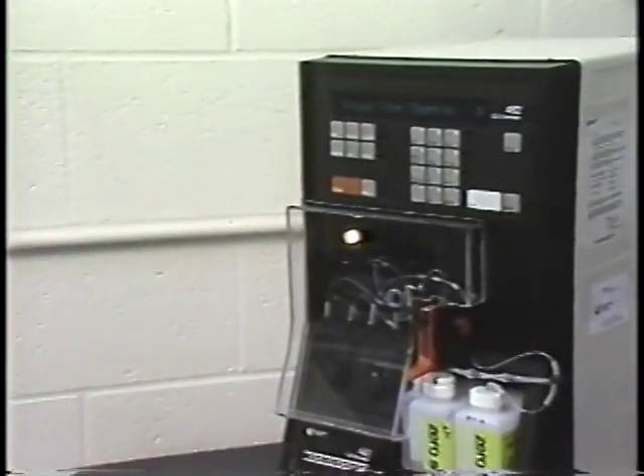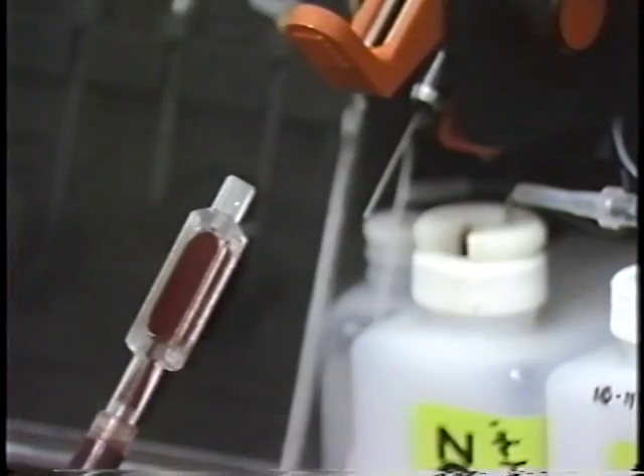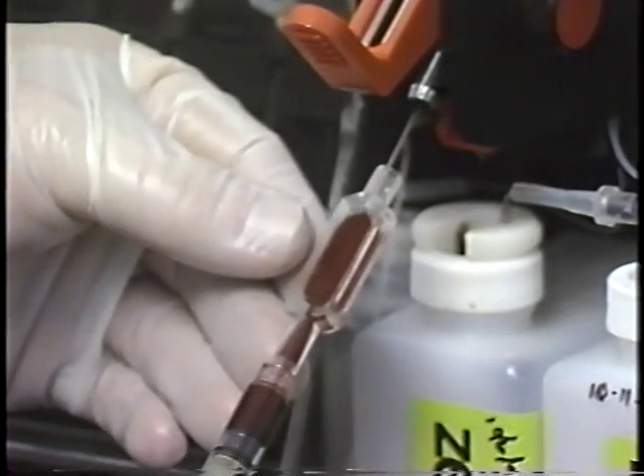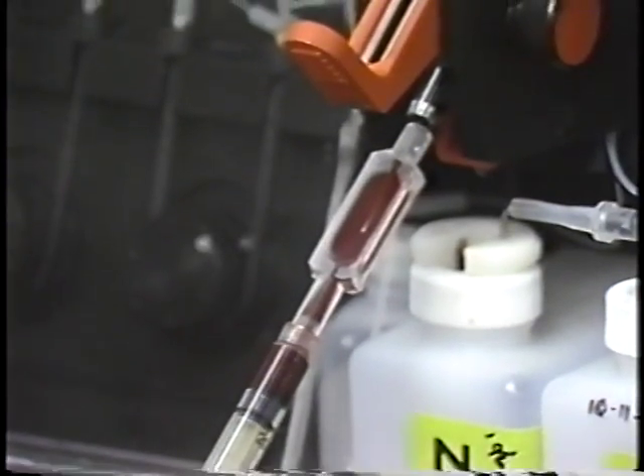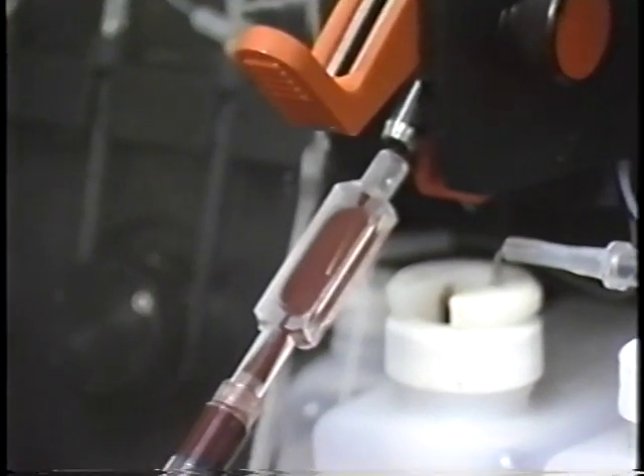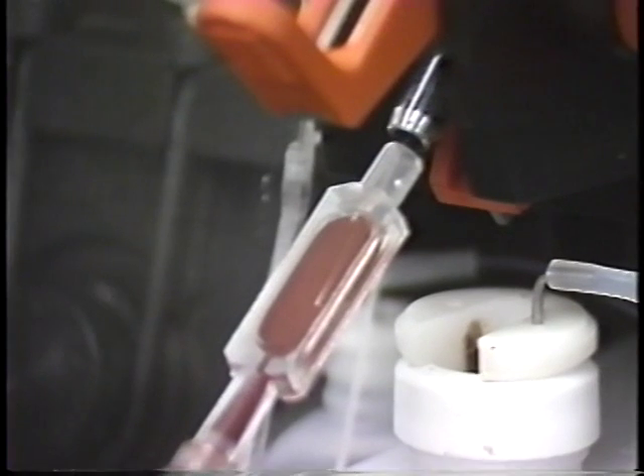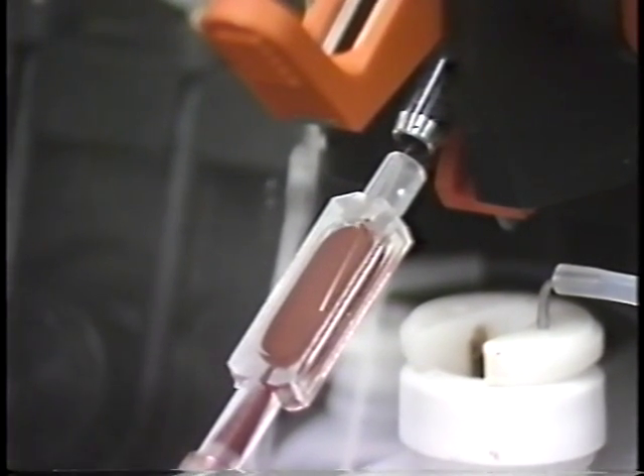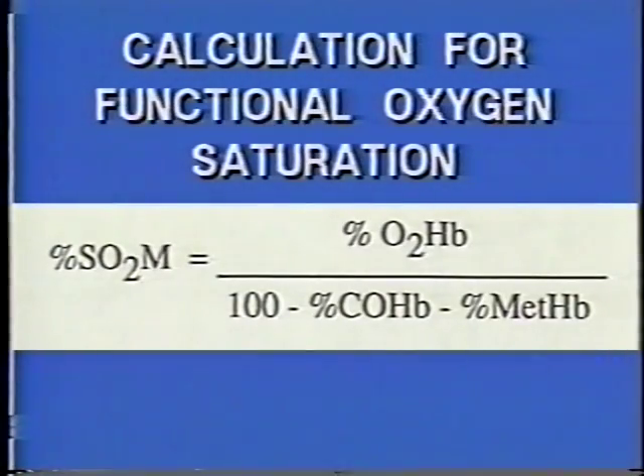Several modern co-oximeters measure oxyhemoglobin, methemoglobin, and carboxyhemoglobin and automatically measure functional oxygen saturation. Measured functional oxygen saturation is required for the calibration of the Oxicom 3000. Some older co-oximeters may not calculate the functional saturation. When using these, the saturation must be calculated manually. The manual formula is: the measured oxygen saturation percent is equal to the oxyhemoglobin divided by 100 minus the carboxyhemoglobin and minus the methemoglobin levels.